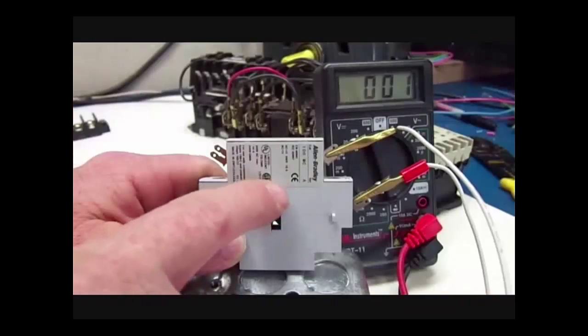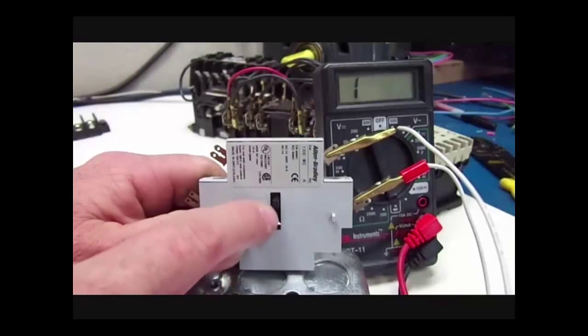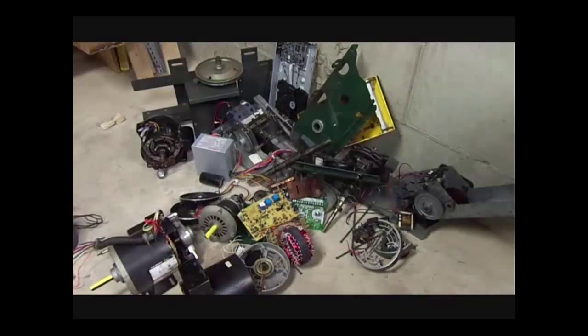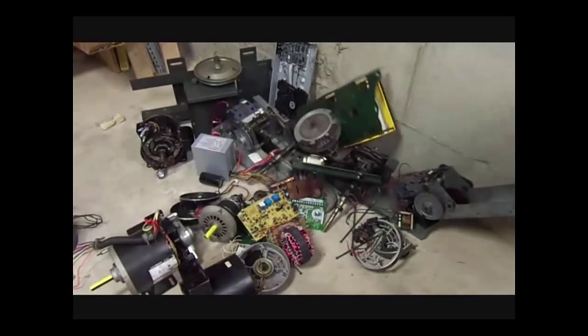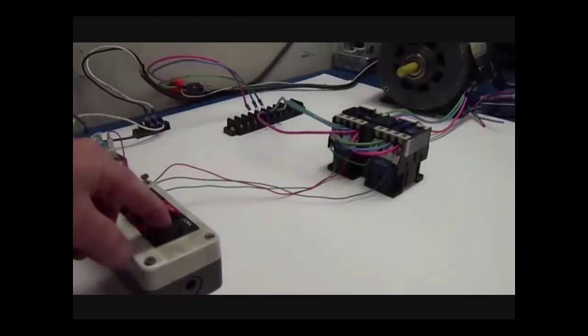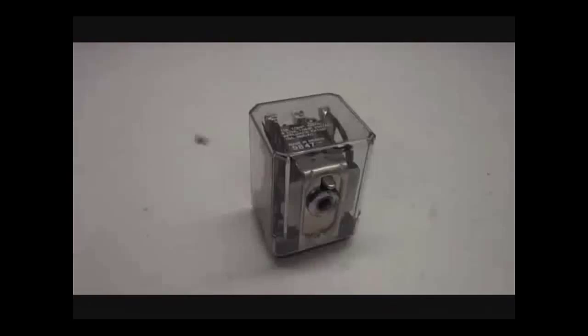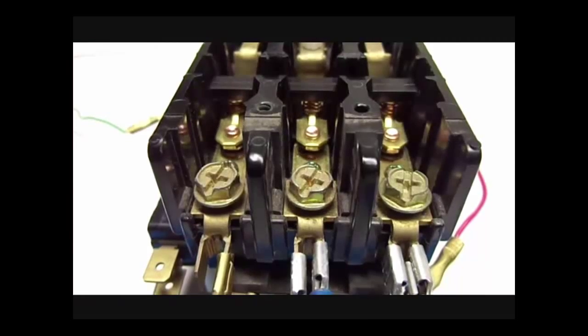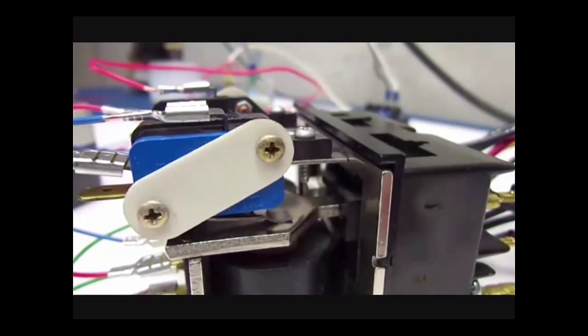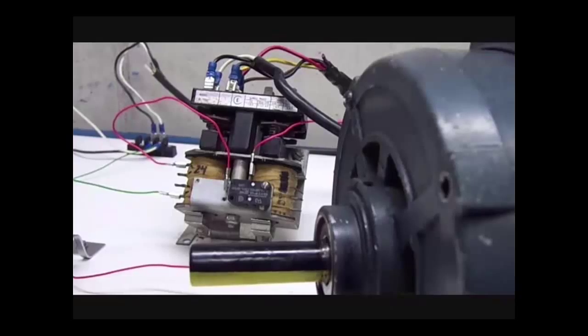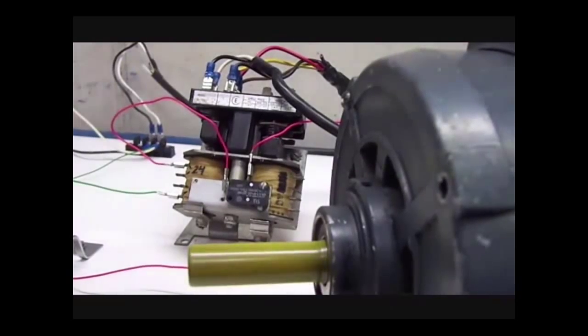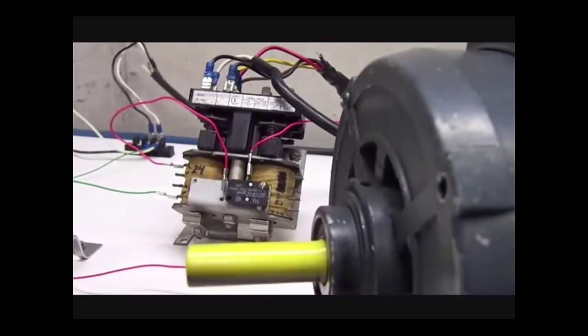We carefully disassemble things to show you their inner workings, and then never quite get around to putting them back together. A contactor is a remote switching device that pretty much does the same thing as a relay, except it's generally rated to handle much higher loads, and they have some unique features. Their most common application is to run electric motors, so that's what we'll be doing here.